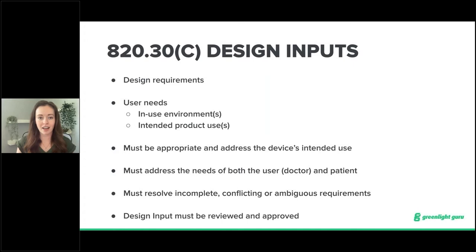Design inputs encompass those user needs, but they need to be separated out and developed by user-facing personnel. They can come through documents like MRDs — marketing requirement documents — or PRDs — product requirements documents. From Part 820, design inputs must be appropriate and address the device's intended use, addressing the needs of both users such as doctors or caregivers, as well as the patient, and anyone else that needs to interact with the device. Manufacturers must also have procedures to resolve any incomplete, conflicting, or ambiguous requirements. Design inputs need to be reviewed and approved.